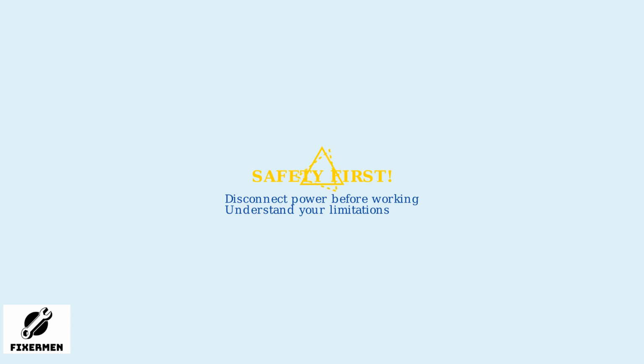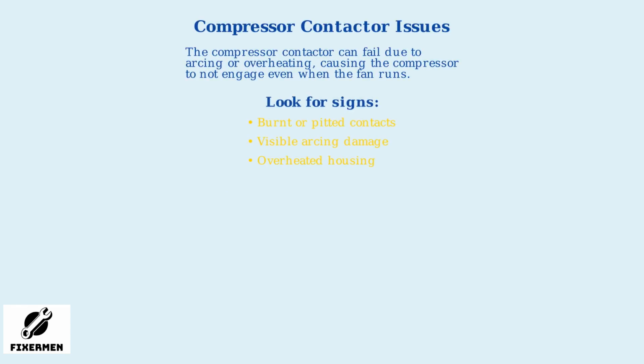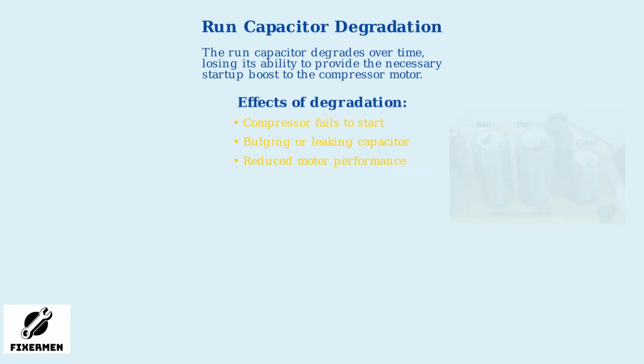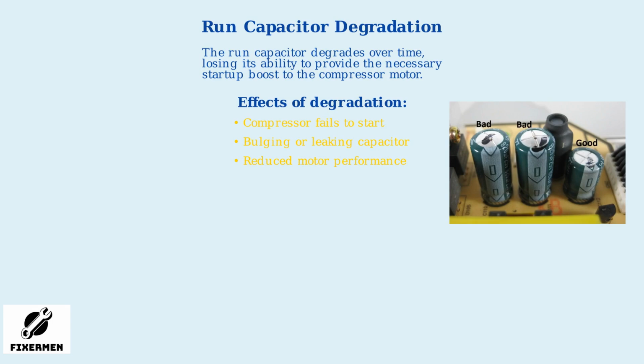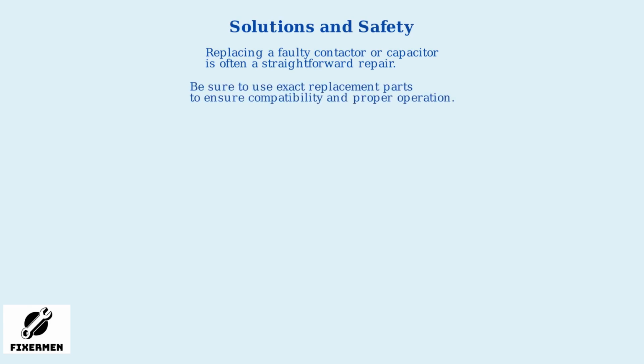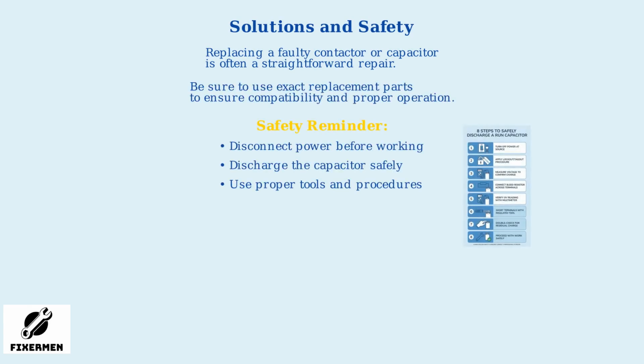Safety first. The compressor contactor can fail due to arcing or overheating. Look for signs of burnt or pitted contacts. The run capacitor degrades over time, losing its ability to provide the necessary startup boost. Replacing a faulty contactor or capacitor is often a straightforward repair. Be sure to use exact replacement parts to ensure compatibility and proper operation. Remember to disconnect power and discharge the capacitor before replacement.